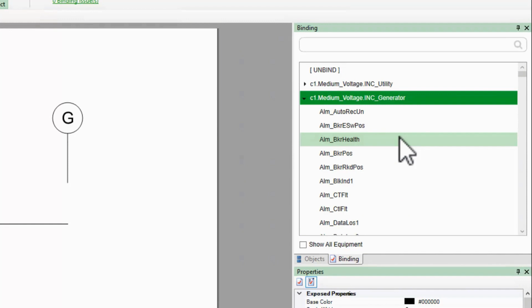However, what if my device is not a smart breaker at all? What if instead I'm reading digital inputs from an electrical meter as my breaker? What if I'm binding the input breaker of a UPS? The ideal situation for digital inputs is that you've used functional addressing to create a concentrated breaker equipment in your database, and I will have videos on this process.